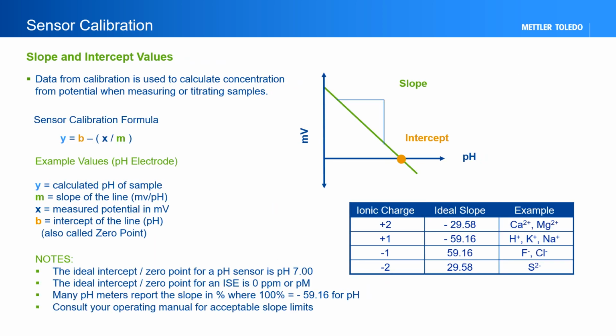Data from the calibration is used to calculate concentration from potential when measuring or titrating samples. This is seen in the example graph and line equation for a pH electrode. Ideal slopes for a sensor depend on the ion being measured. Most ideal slopes are displayed in the table. The ideal zero point for a pH sensor is pH 7, and for sensors measuring in parts per million or PPM values, it is 0 parts per million or 0 PPM.